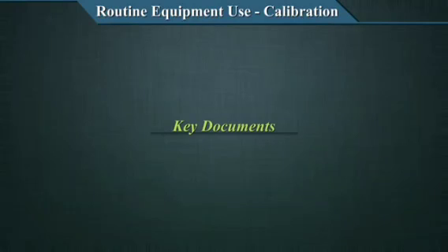If you remember, if calibrations are done, generally it's a precision check before and after your calibration. Before calibration, the precision check is done to understand whether there are errors, so that random errors are corrected. And after calibration, for verification of your calibration and running of your calibrator, all these things should be retained. There will be a lot of raw data generated during your calibration of your analytical equipment.